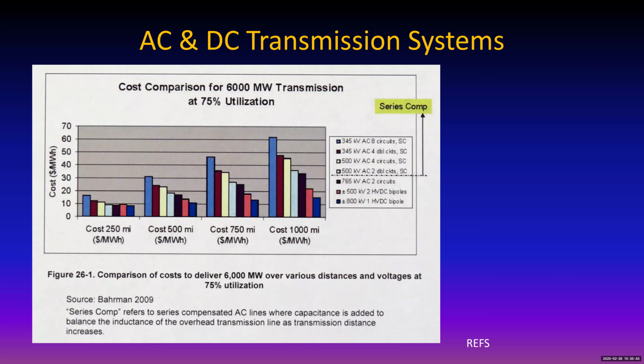With DC, you use the entire cross-sectional area of the wire at the same rate of flow throughout. Now, DC you have to convert at the beginning, so that costs money, and you have to convert to AC at the other end of the line, so that costs money too. So for the longer distance, you have that fixed cost at the beginning and end of the line, but the cost of the line itself—the losses—increases significantly slower for a DC line than for an AC line.